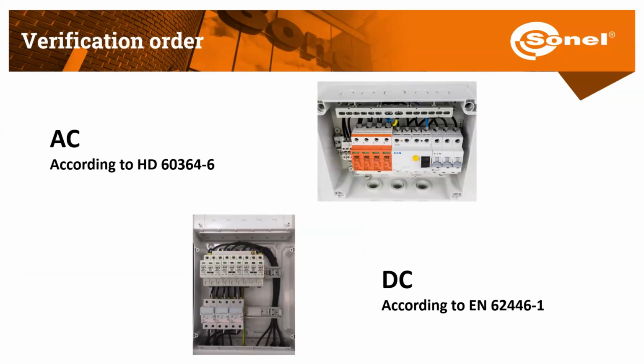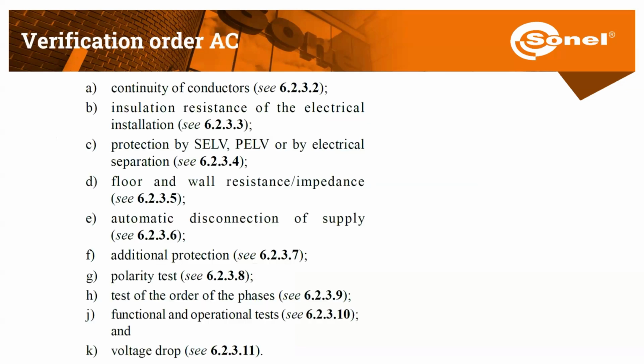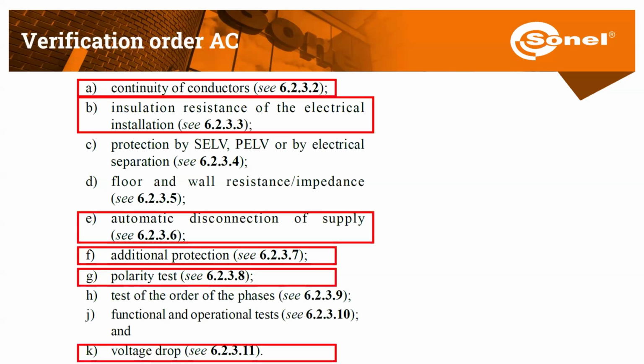We inspect the AC side in the same way as a low voltage installation following IEC 60364 part 6. In India, the standard is known as IS 732. The measurements described in the IS 732 standard, specifically clause 6, include continuity testing of protective connections, insulation resistance testing, automatic disconnection of supply by measuring the loop impedance, additional protection testing by checking the RCD's parameters, and polarity testing. I think this is 1, 2, 3, 4, 5, 6. These 6 measurements are the core of the measurements in a PV system. In a small PV system, if we are talking about a PV power plant, the measurements will be different.